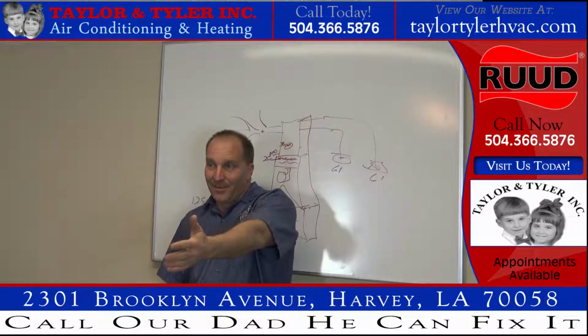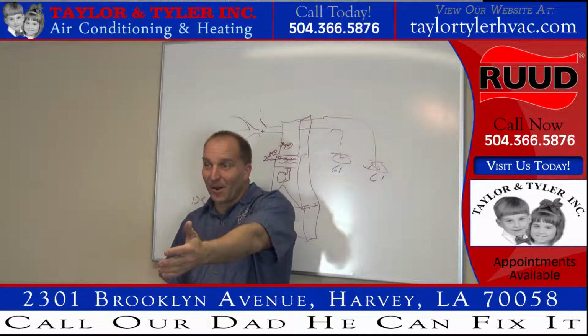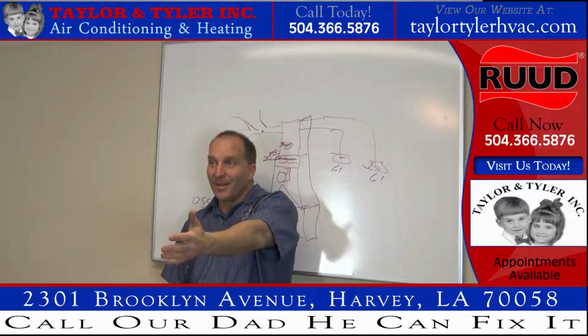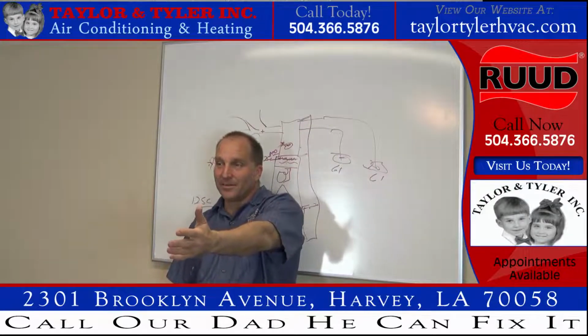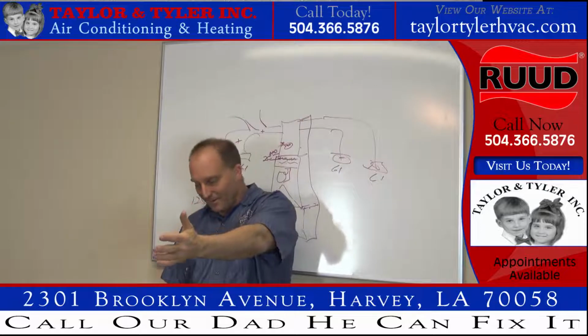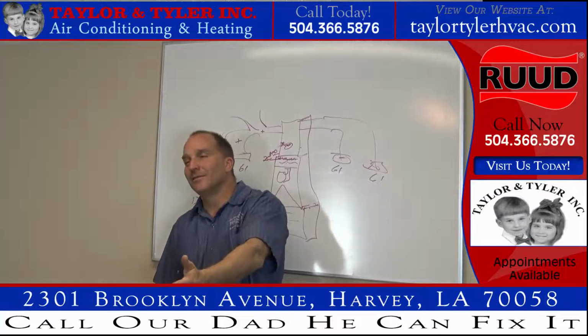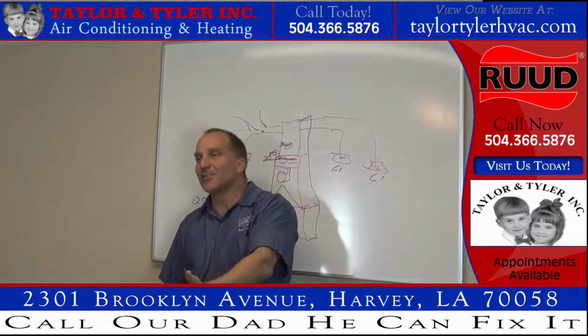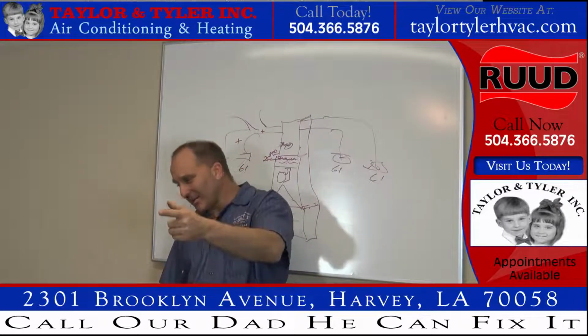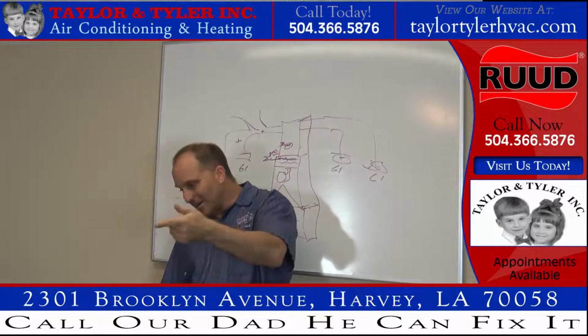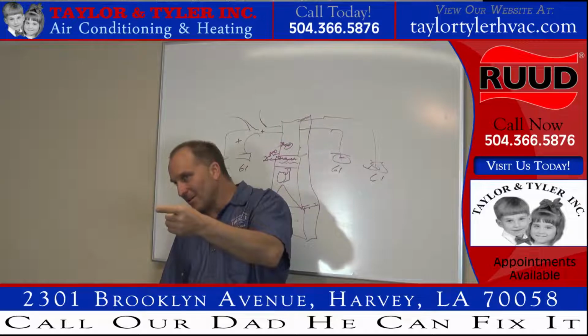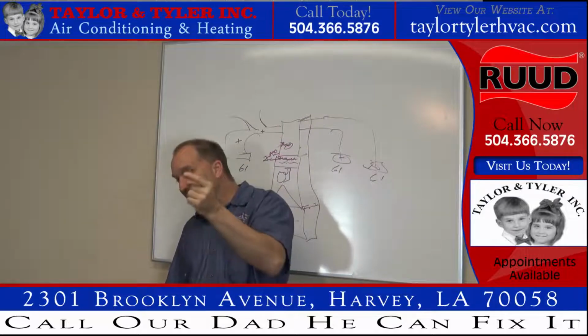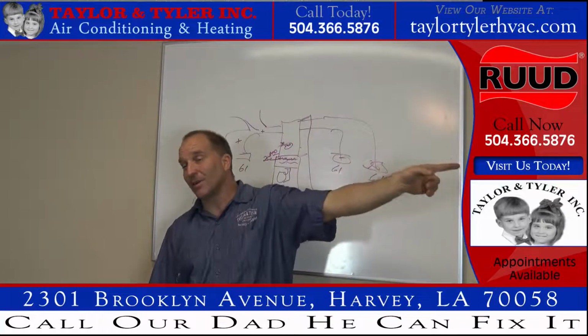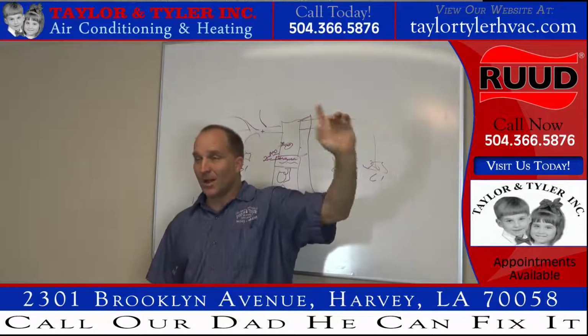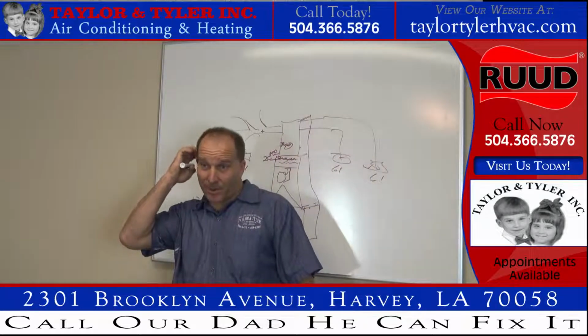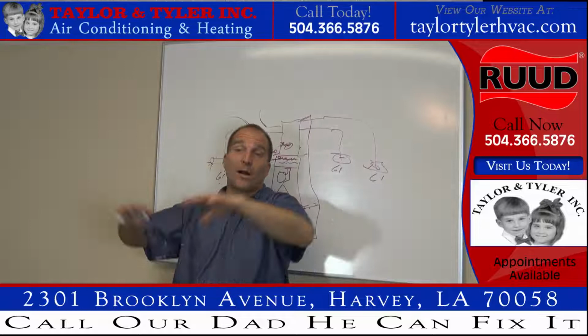R801, 075, that's 75,000 BTU. 417, it's a 4-ton, 17 inches wide. What size coil did I say you had? 2-ton, RCF 2417, right? What size condenser did I say you had? 3-ton. So now, did you lower the blower speed on the furnace when you installed it, or whoever installed it?